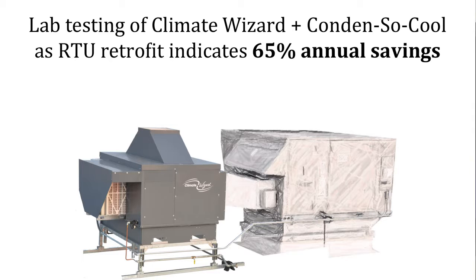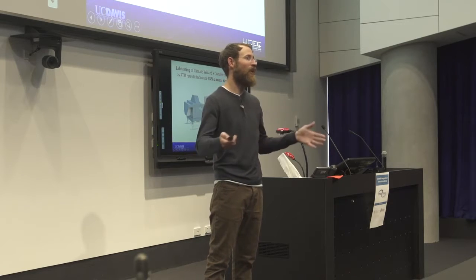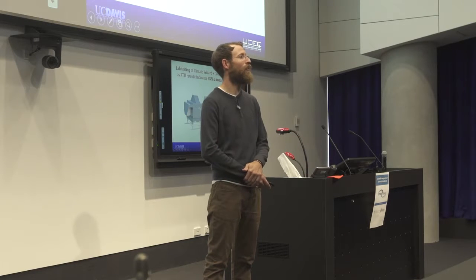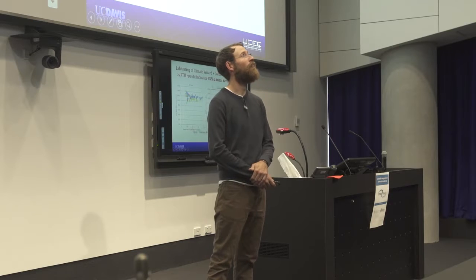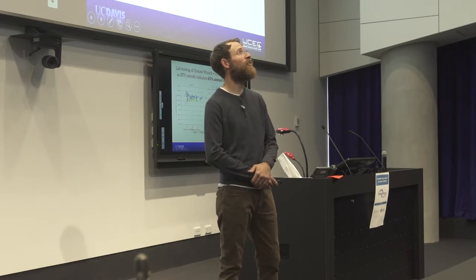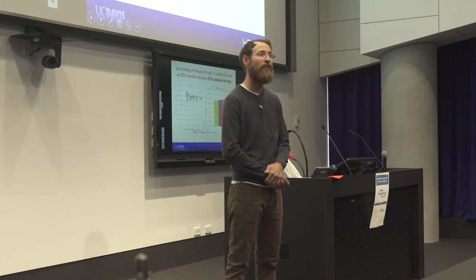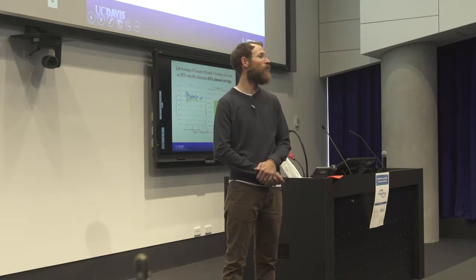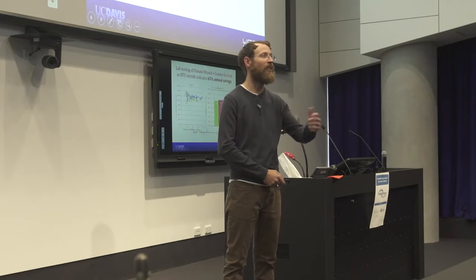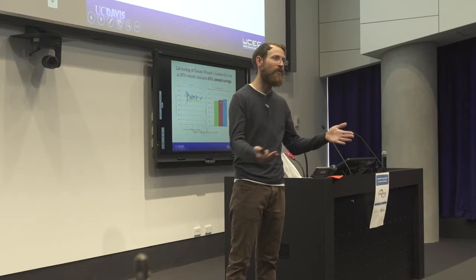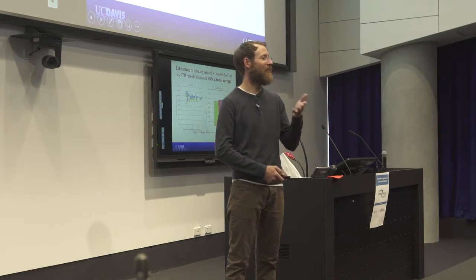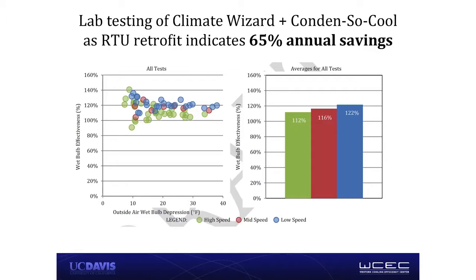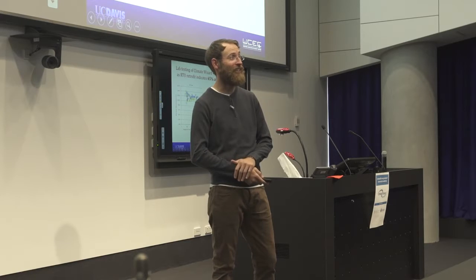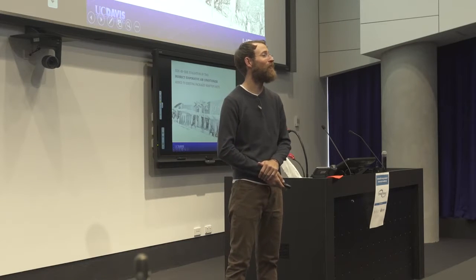That's using a load-weighted assessment of all of the different cooling hours in the course of the year for a California commercial building. Here's an example of the results for the wet bulb effectiveness, which is a measure of how close that system cools to the wet bulb temperature. Remember, usually an evaporative cooler would only be able to cool towards the wet bulb temperature, but this shows very clearly that the Climate Wizard cools well beyond the wet bulb temperature. We're getting up well above 110, 120% wet bulb effectiveness. It's really interesting to see the technology capable of doing this by evaporation.